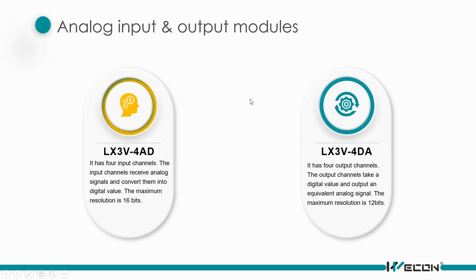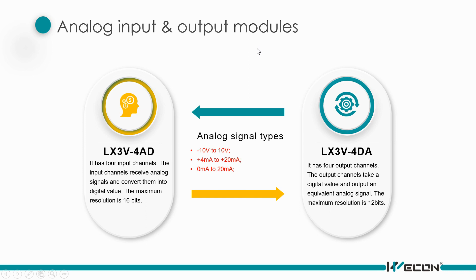Here are the analog input and output modules — AD and DA. They can support voltage signal or current signal. The voltage signal ranges from -10V to 10V, and the current signal ranges from 4mA to 20mA, or 0 to 20mA.